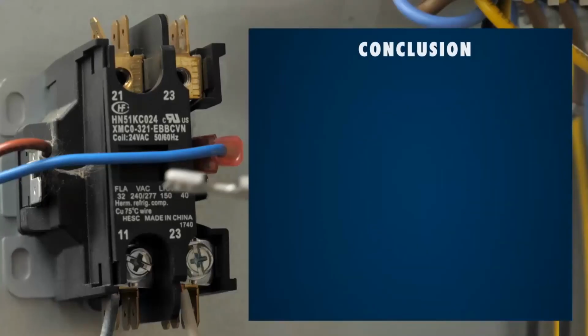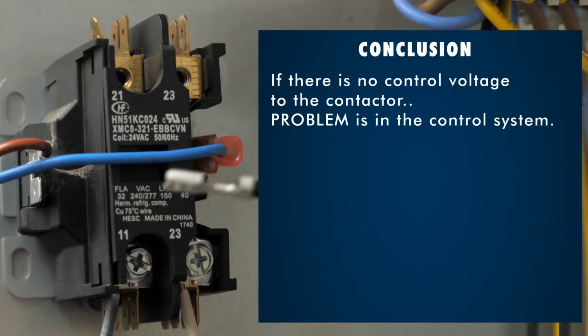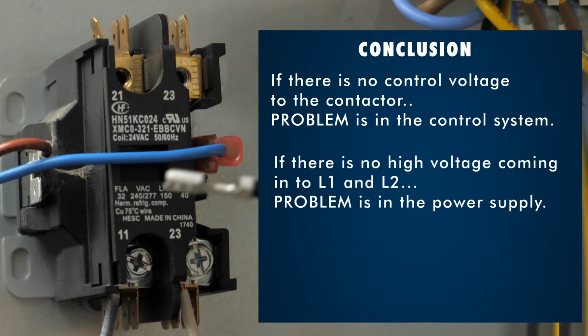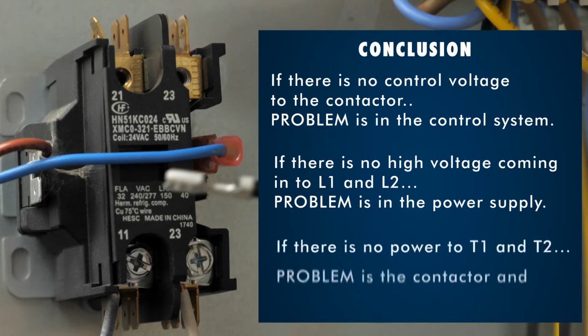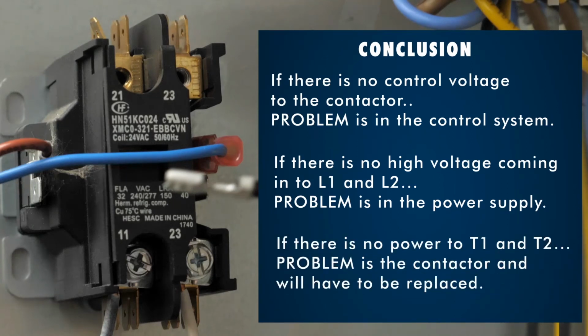In review, if there's no control voltage to the contactor, the problem is in the control system. If there's no high voltage coming to L1 and L2, the problem is in the power supply. If there's no power to T1 and T2, the contactor will have to be replaced.